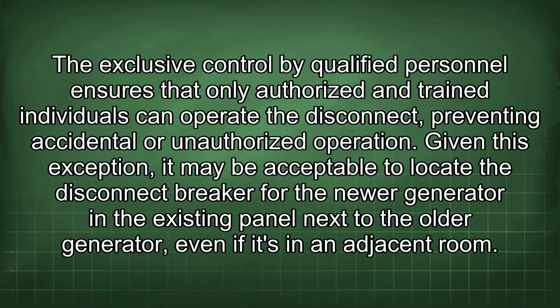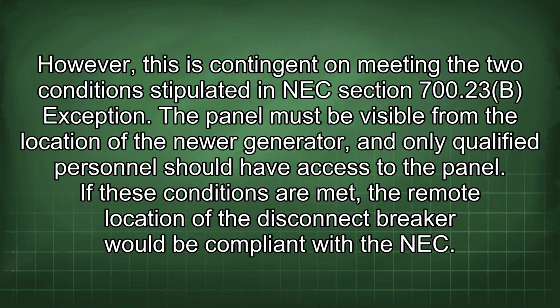The exclusive control by qualified personnel ensures that only authorized and trained individuals can operate the disconnect, preventing accidental or unauthorized operation. Given this exception, it may be acceptable to locate the disconnect breaker for the newer generator in the existing panel next to the older generator, even if it's in an adjacent room. However, this is contingent on meeting the two conditions stipulated in NEC Section 700.23b exception. The panel must be visible from the location of the newer generator, and only qualified personnel should have access to the panel. If these conditions are met, the remote location of the disconnect breaker would be compliant with the NEC.